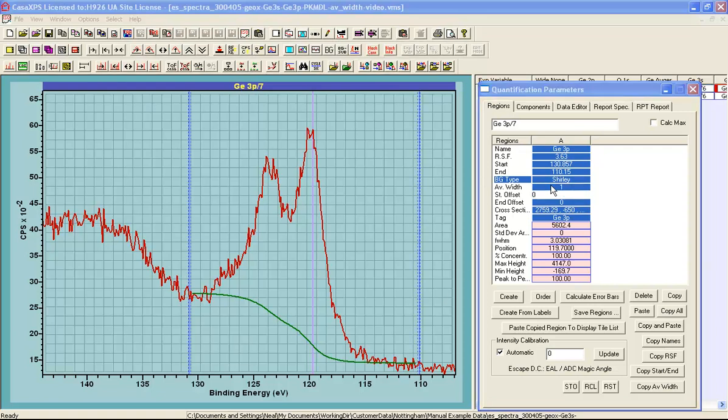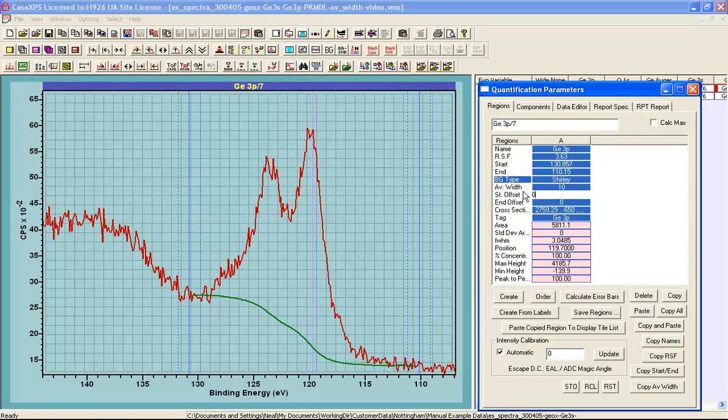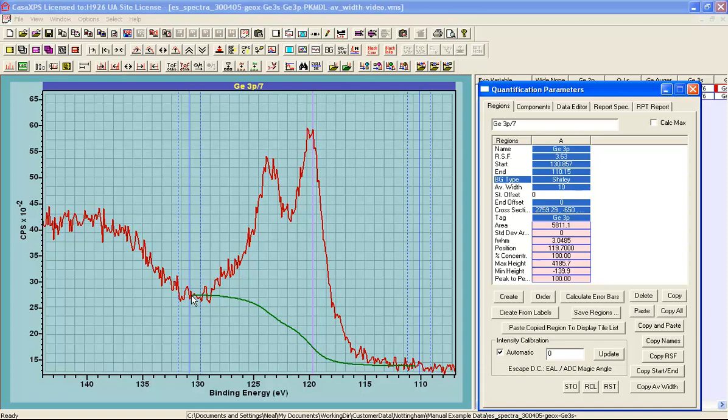The average width allows us to specify an interval over which the intensity is calculated from more than one data bin. So when I specify 10, I am actually specifying 10 points outside of the interval and 10 points inside of the interval. And the average of these intensities are used to work out a value that can be assigned to the background at this end of the energy interval. And a similar calculation is performed at the other end of the interval.